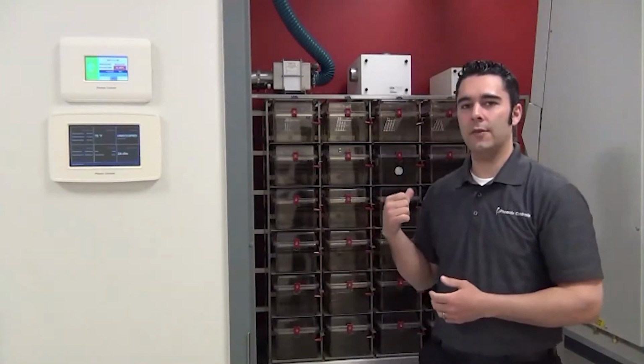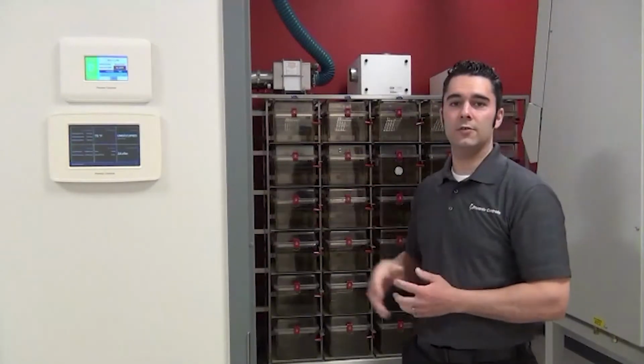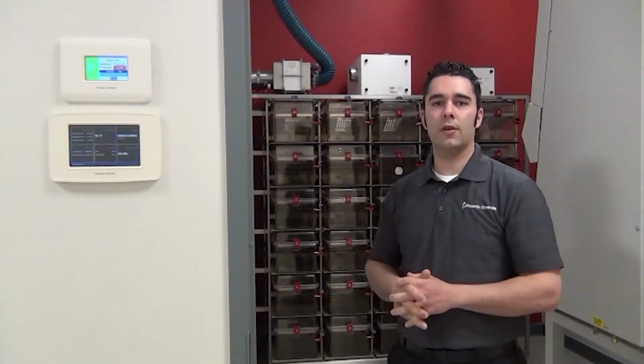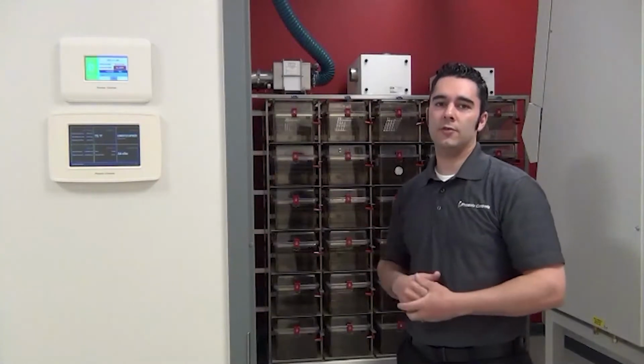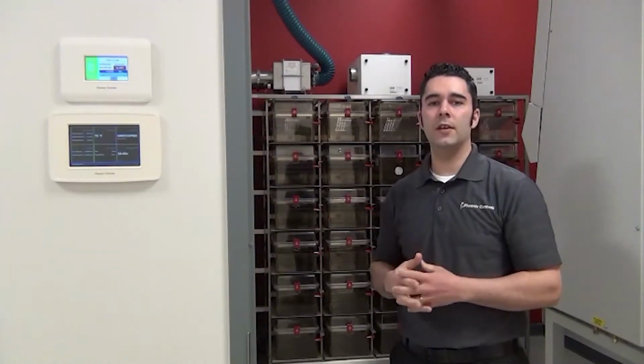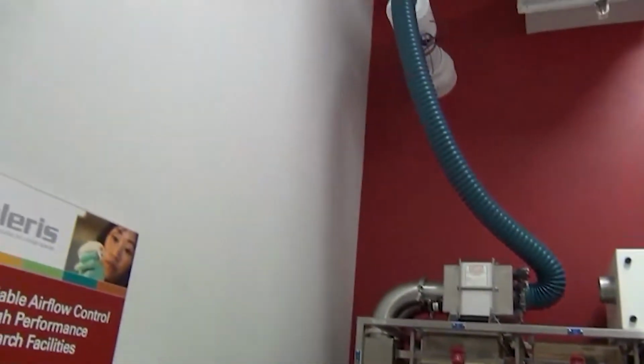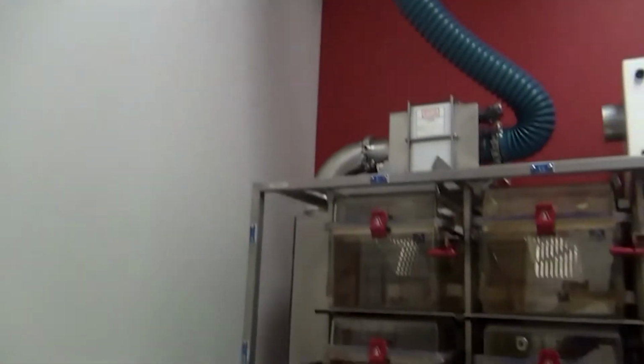As part of the Phoenix Controls research demonstration suites, I have behind me a biocontainment room. Now, what you see in this room may not be 100% typical of what you would see in every biocontainment room. However, we are trying to show a lot of the features of the Phoenix Controls equipment in the real environments where they would be acting. So what I have directly behind me is a large cage rack, an animal cage, and effectively how the Phoenix Controls product works with this cage rack is we have a special cage rack valve. And effectively it is a valve that has a smaller inlet and outlet diameter so that you can put the hoses from that cage rack directly onto the top of the cage and right into the Phoenix Controls valve.